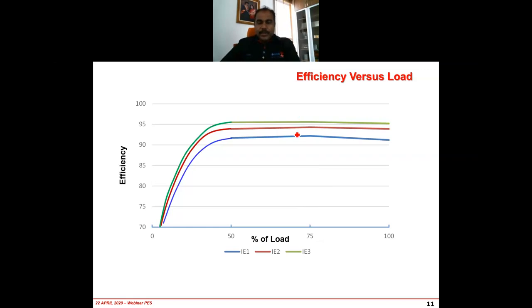Just imagine, let's say I have an IE1 motor, which is operating at about 80%. That means here, this is the IE1 motor, okay? Now I have another system, which is IE3, the green one, but it is operating at 40%. Let's say the load on that particular system is so light, or in other words, the motor was actually oversized. That means it's operating at a light load. You can see here, even though I'm using IE1, the efficiency is higher compared to the IE3 motor because the load is actually low.